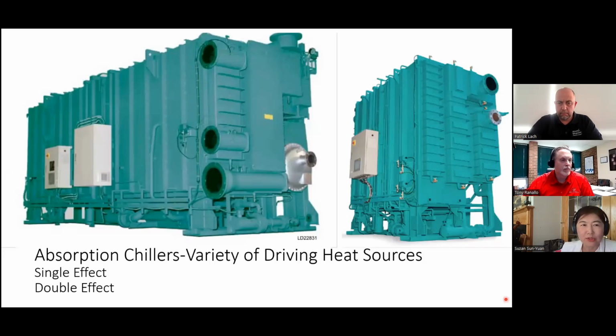Both absorption chillers shown on this slide use lithium bromide water solution. The double effect on your left, you can see, uses steam as the driving source. The single effect type is the one on your right, which uses hot water with the flanged connection. Next slide, please.